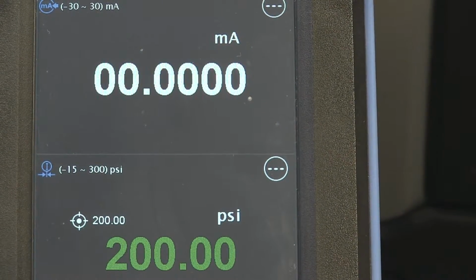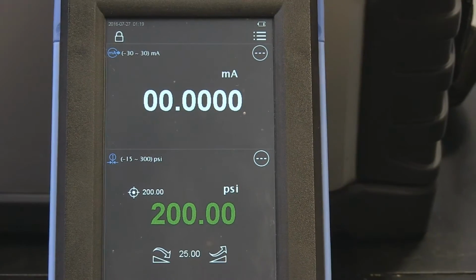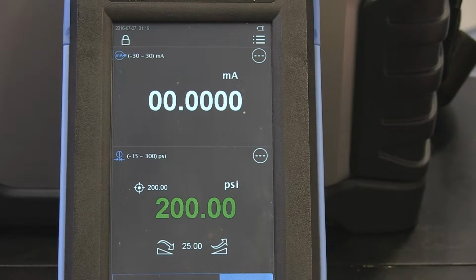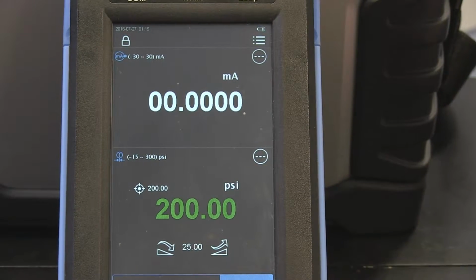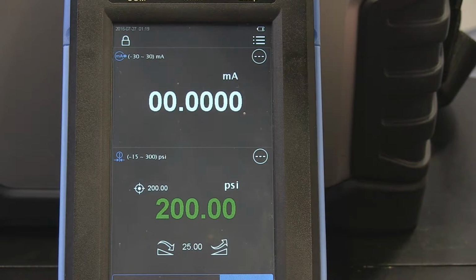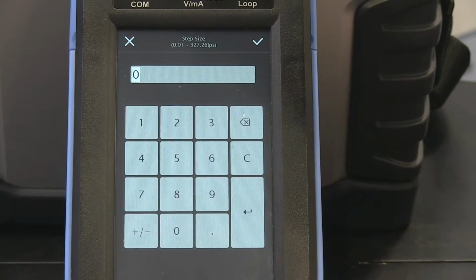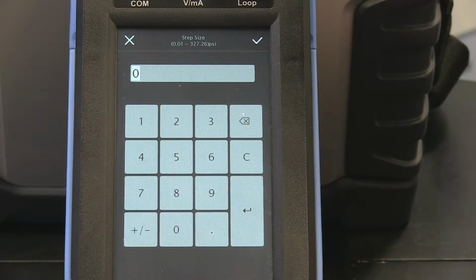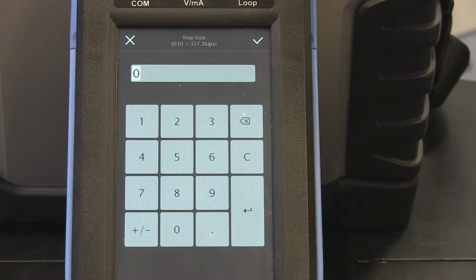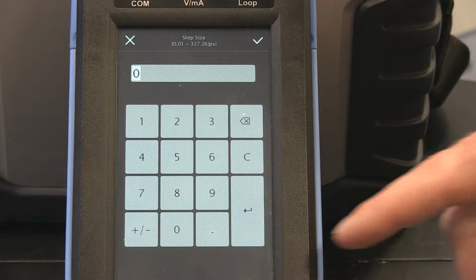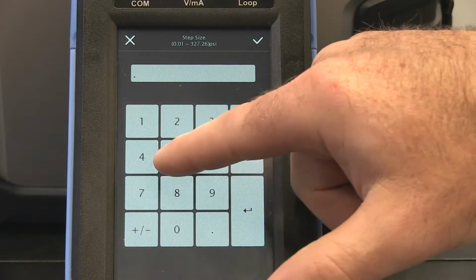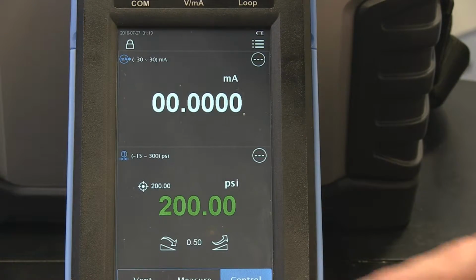So right now it's a vacuum to 300 PSI module that we're currently using? Yeah. Okay. So if I put in a different sensor, switched it out for one that's a lower range, say 100 PSI, it would display that there. So it's right on the front telling you this is the range you can cover. We have a little jog function here, which you can set the pressure you want for it. So say you have a dial gauge and you want to hit a cardinal point, and maybe we need to increment that a half of a PSI, for example. So now my jog pressure is a half of a PSI as shown there.